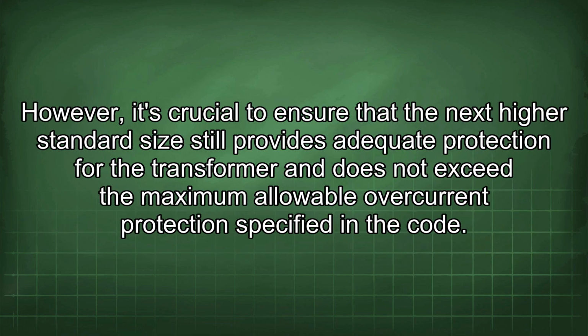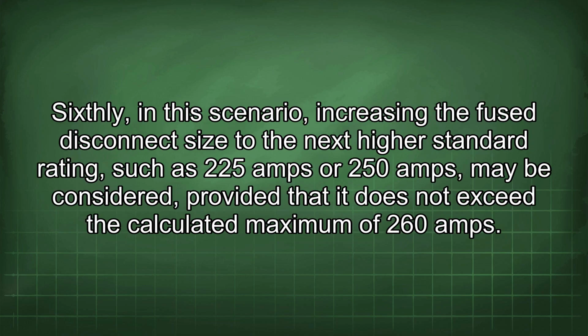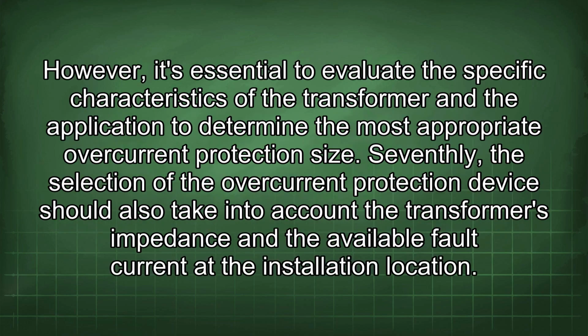However, it's crucial to ensure that the next higher standard size still provides adequate protection for the transformer and does not exceed the maximum allowable overcurrent protection specified in the code. Sixthly, in this scenario, increasing the fused disconnect size to the next higher standard rating, such as 225 amps or 250 amps, may be considered, provided that it does not exceed the calculated maximum of 260 amps.